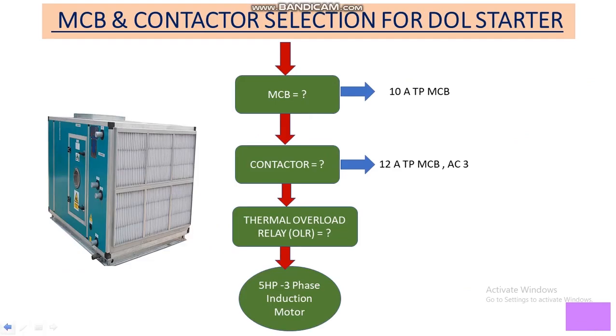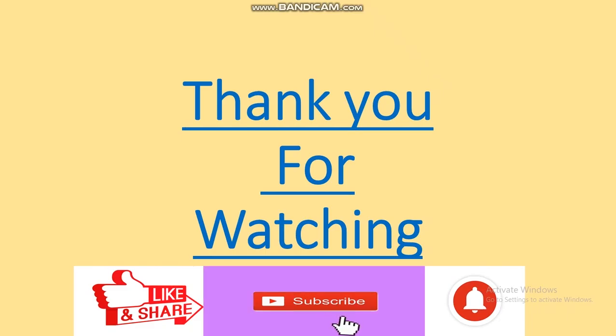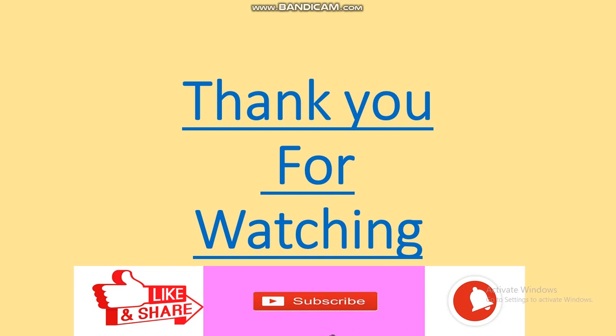Finally, our calculated results: for this AHU's DOL starter, the MCB size is 10 A TP MCB and the contactor size is 12 A TP AC3 type. In this video, we have selected the MCB and contactor. In the next video, we will talk about thermal overload relay sizing and selection. Hope you guys understand how to select the contactor and MCB for a DOL starter. Thank you for watching — please like, share, comment, and subscribe, and hit the bell icon for notifications. Thank you very much. See you again in the next video.